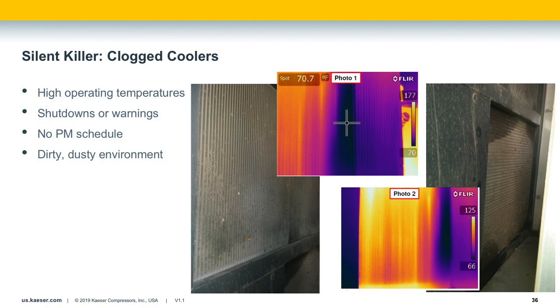This site suffered from lack of maintenance. The oil changes were not done as necessary. The oil filters did not get changed until there was a differential pressure alarm on the filter, and good housekeeping practices of simply cleaning filter mats and coolers were not followed. These units were able to be salvaged by running a cleaning solvent through the oil circuit, removing the majority of blockage. The coolers were not 100% effective after the cleaning, and replacement was recommended.